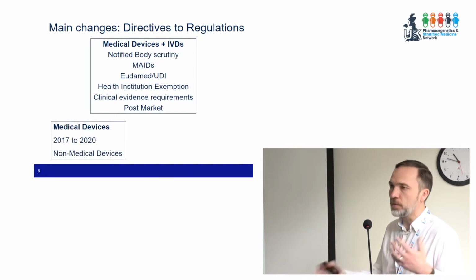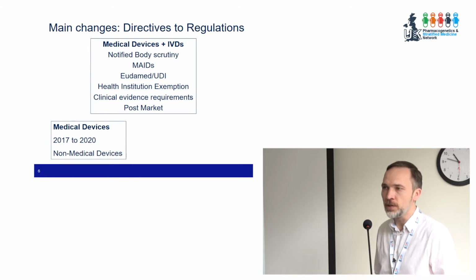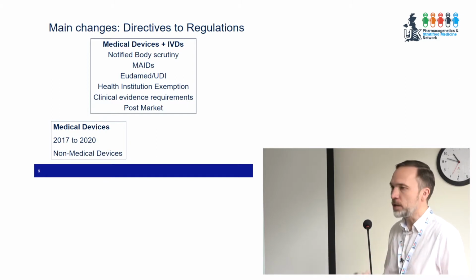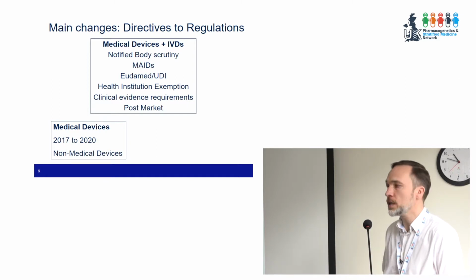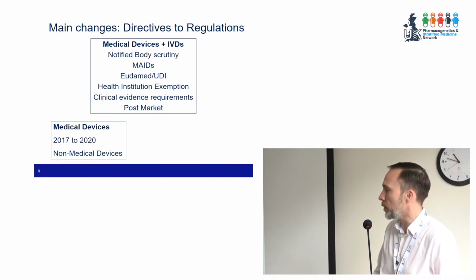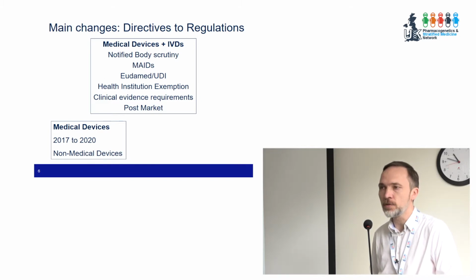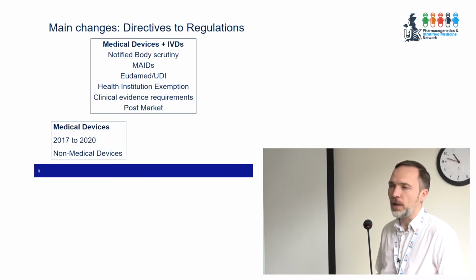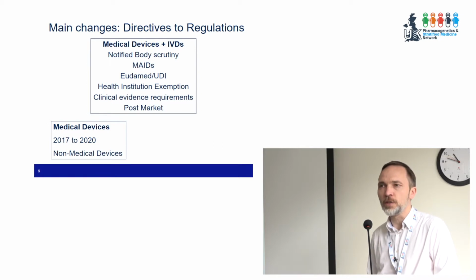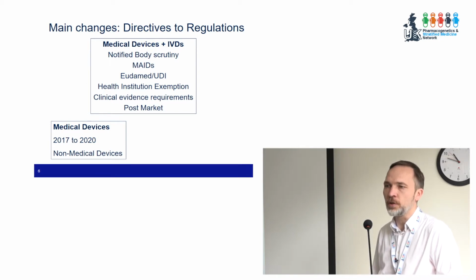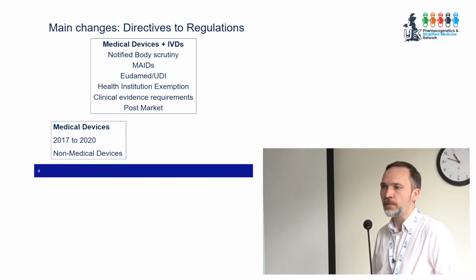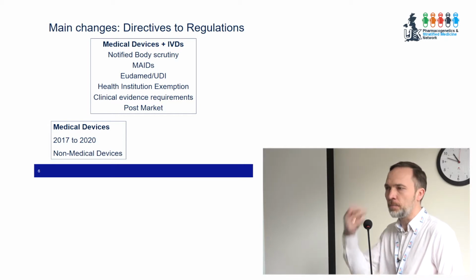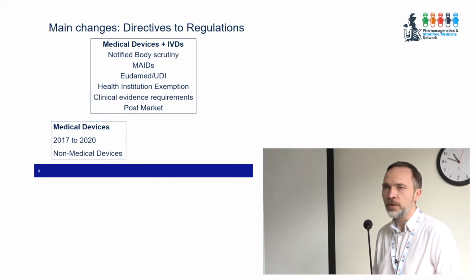Specifically, there are two sets of regulations, one for medical devices, one for IVDs. So most of these apply to both medical devices and IVDs. The medical device regulations were published in 2017, and they are going to be fully enforced in 2020, so just next year, in May next year. I find this really kind of strange, these non-medical medical devices, things like cosmetic products, which are listed in the medical devices regulations. I don't think there are any software products in that list, but it's things like plano contact lenses and lip fillers, that kind of stuff.